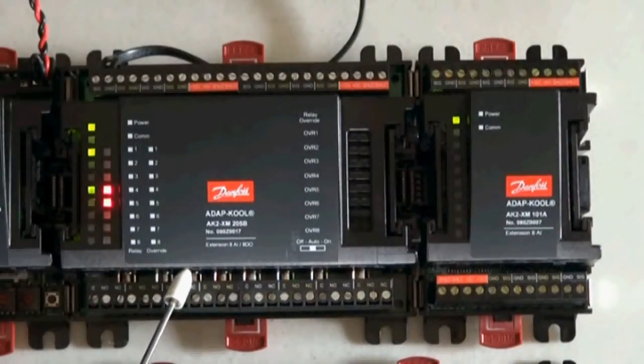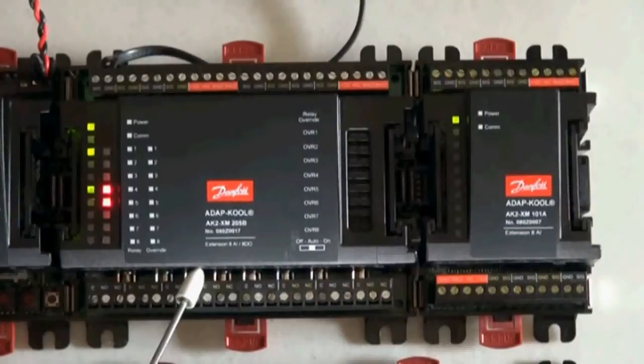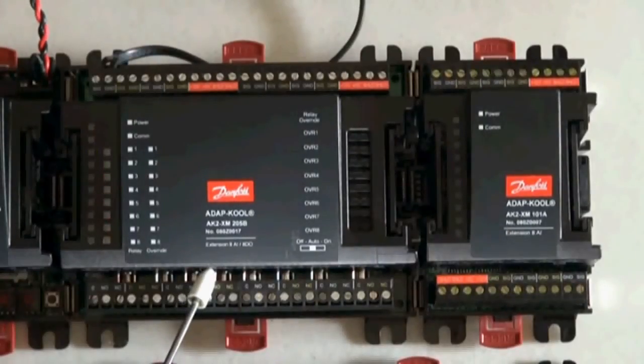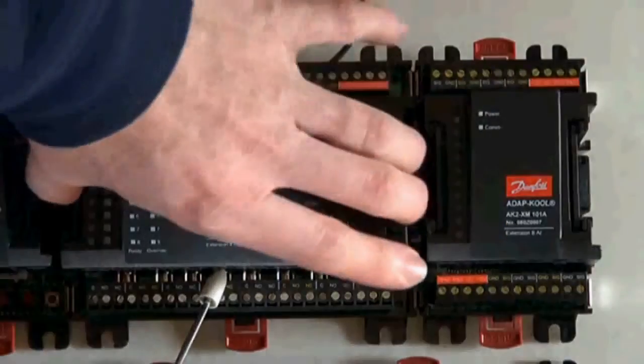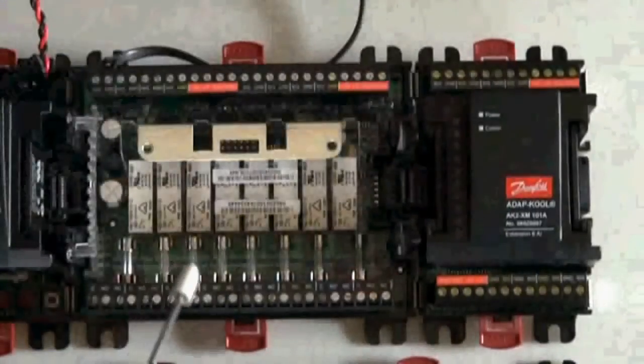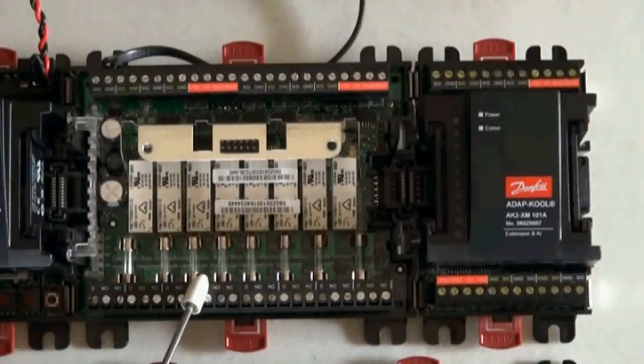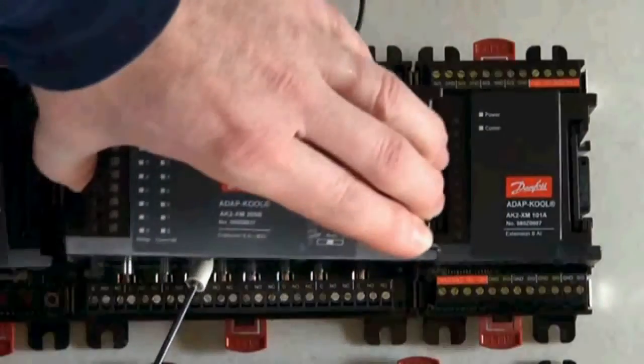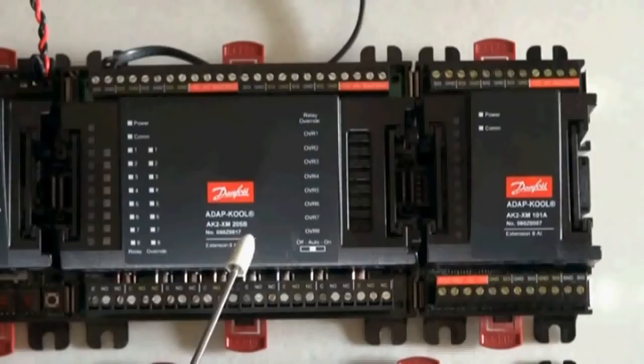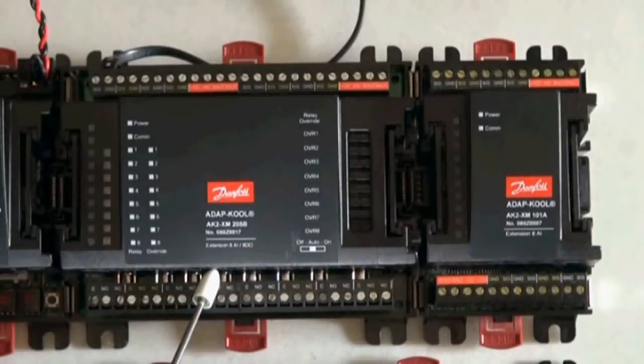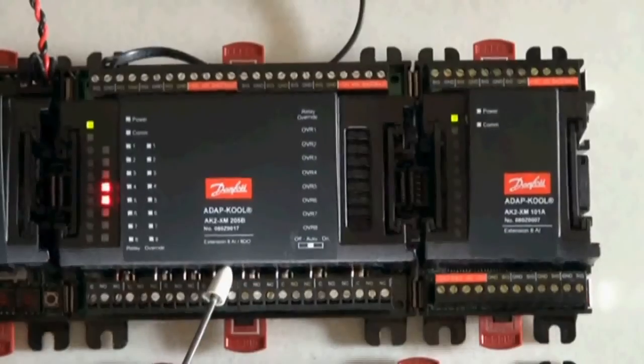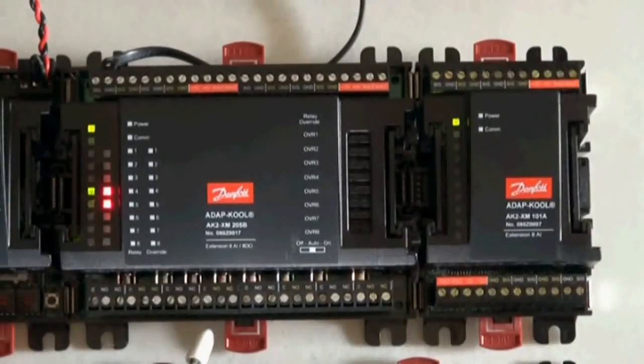To remove the cover to get to the fuse locations, first depower the communication module. Next, squeeze the right and left side plastic strips and pull toward you. Here we see the location of the 5 amp fuses. To return power to the board, replace the override switches and the cover and power up the communication module.